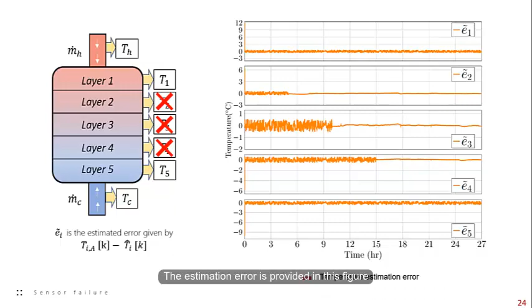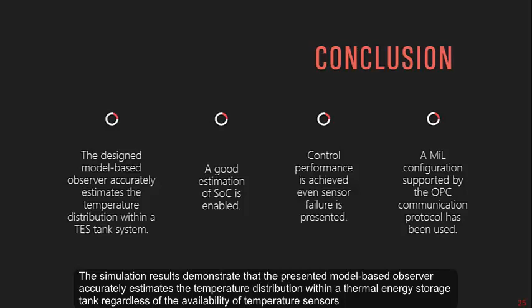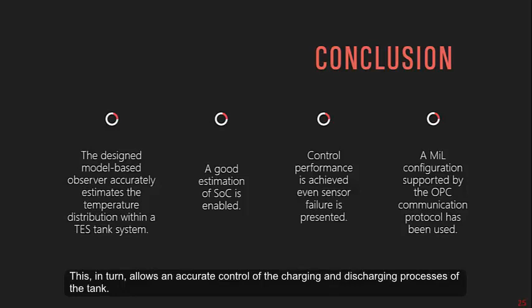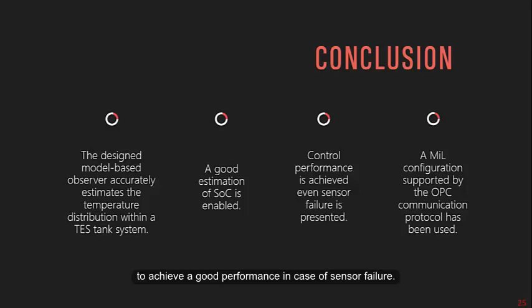The simulation results demonstrate that the presented model-based observer accurately estimates the temperature distribution within a thermal energy storage tank regardless of the availability of temperature sensors for the internal layers along the tank's height. As a result, this enables a good estimation of the system state of charge. This, in turn, allows an accurate control of the charging and discharging processes of the tank. The observer is capable of supporting the operation of the control system to achieve a good performance in case of sensor failure. A model-in-the-loop configuration supported by the OPC communication protocol has been used. This has enabled real-time co-simulations between MATLAB and APROS.